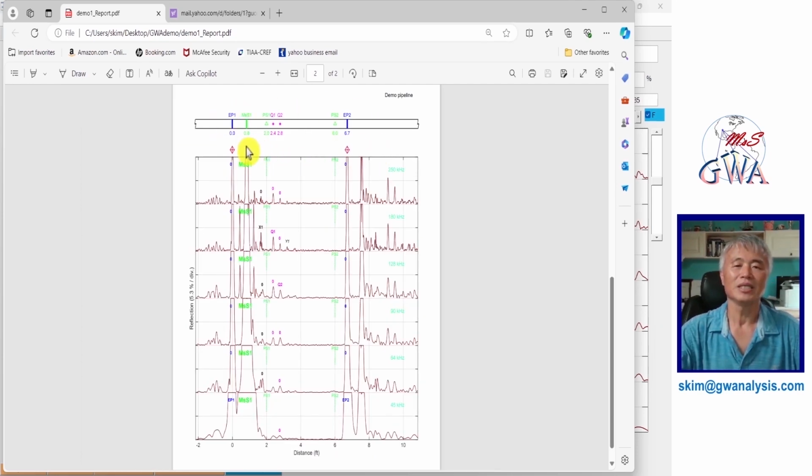The second page is a schematic drawing of the tested pipeline with all findings. The two diamonds at the EP1 and EP2 locations show the inspection range. All UT findings were marked on the top of the signal, but all visual testing findings were marked with a green dotted line for differentiating.